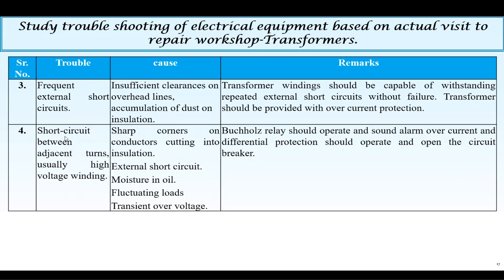Next one is short circuit between adjacent turns, usually of higher voltage winding. The causes are sharp corners on the conductor cutting into insulation, external short circuit, moisture in oil, fluctuating loads, transient over voltages. The remark is Buchholz relay should operate and sound alarm, over current and differential protection should operate and open the circuit breaker.